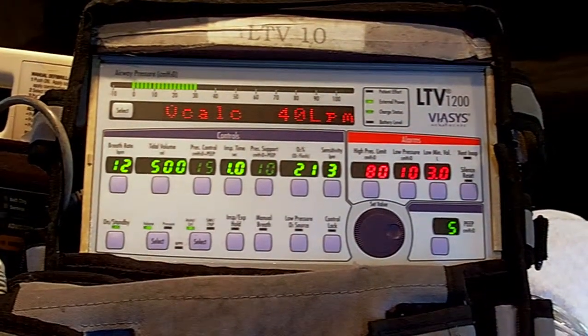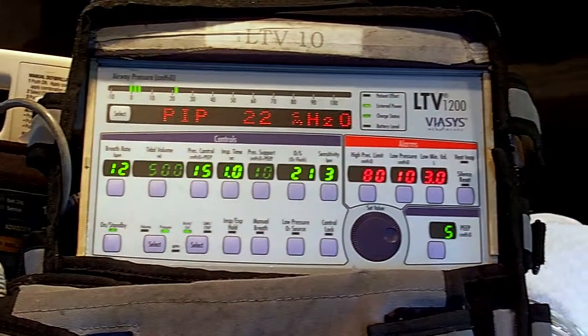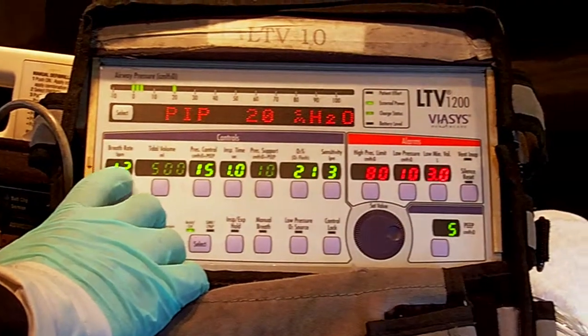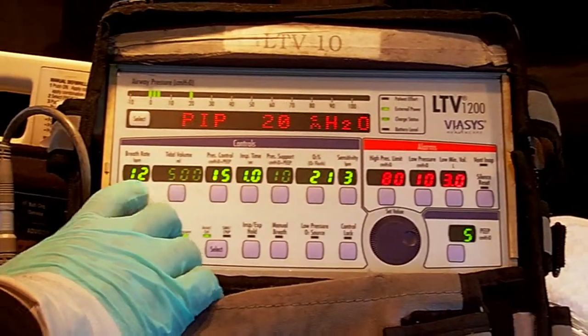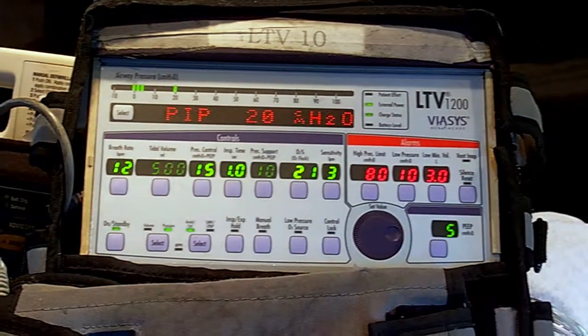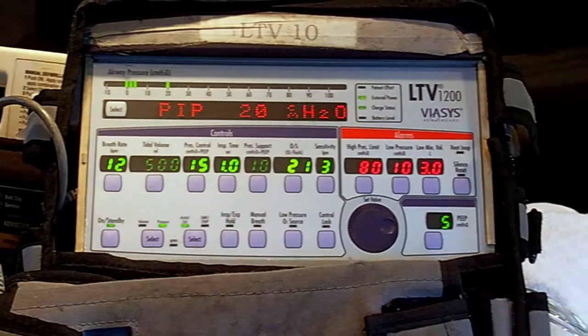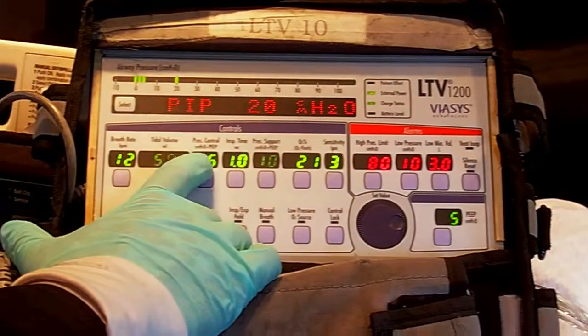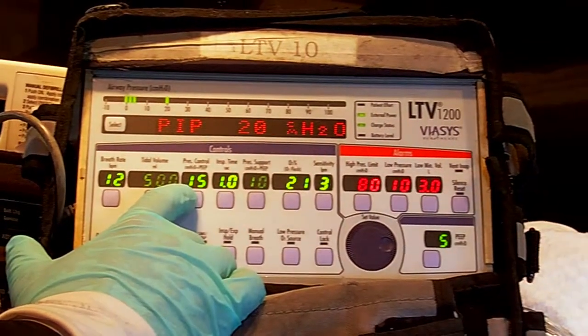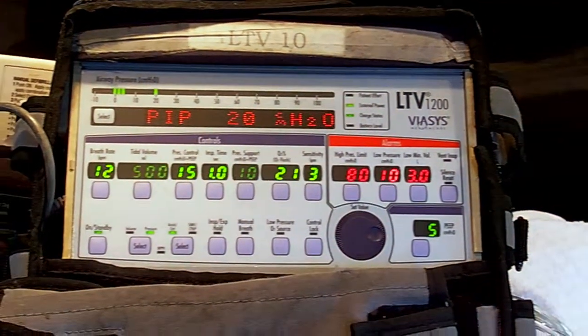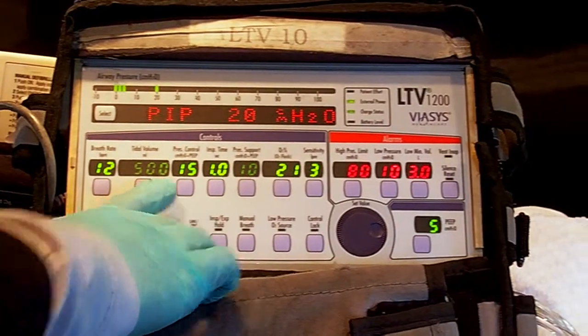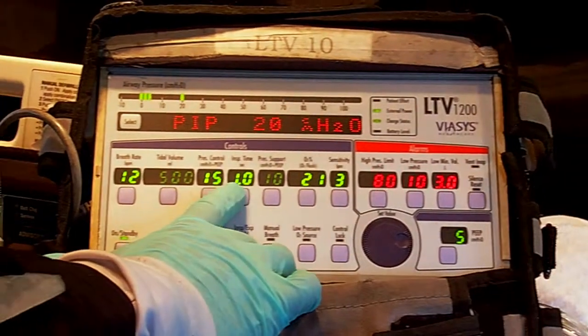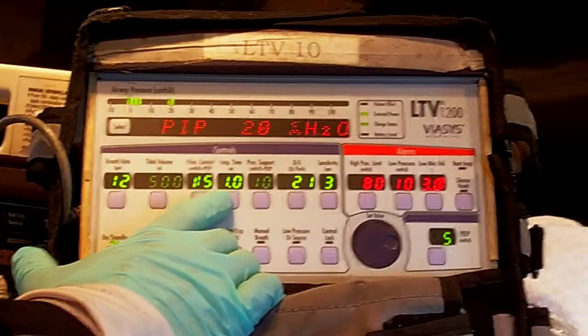The third breath type is pressure control. The trigger is going to be breath rate — 12 breaths a minute, one breath every five seconds — so it's elapsed time. In pressure control, trigger is set time, target is pressure — in this case 15 centimeters of water pressure. And our cycle is going to be the inspiratory time, or I-time — in this case, one second.